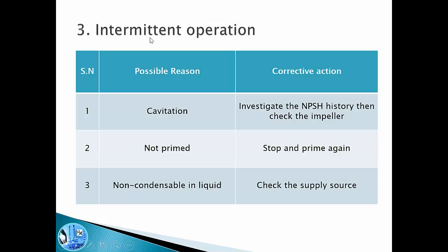The third problem is intermittent operation. The reason could be cavitation, and we need to check the impeller mechanically. Maybe the pump is not properly primed, so we need to stop, check, and prime it again. Maybe non-condensables are coming with the liquid, and in that case we need to check our supply sources.